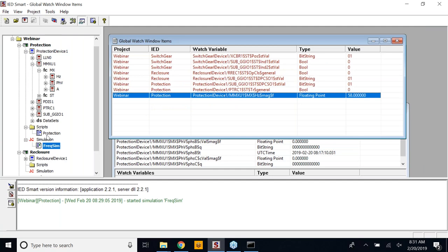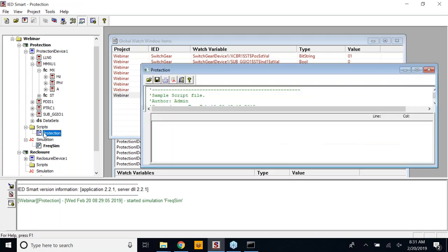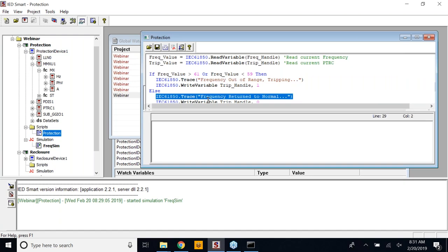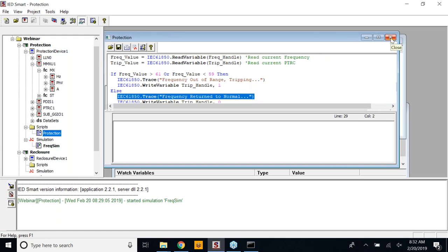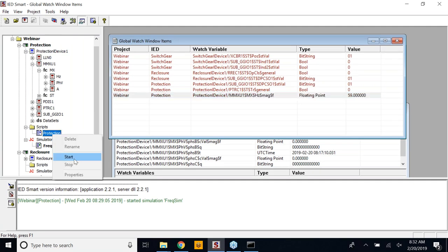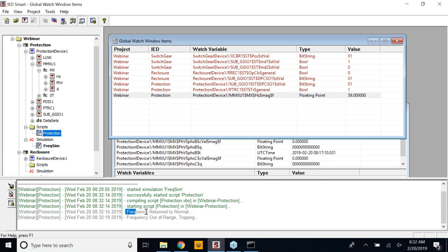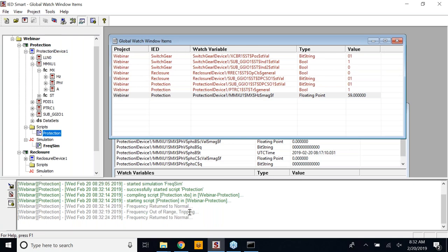I will run the script. There are certain print statements available and a trace — you will be able to see these two traces as the system detects these signal conditions. I will run this manually. Now you could see that the frequency has returned to normal — that's the first condition triggered — and now it is tripping. As the signal crosses 61 to 62, the trip signal will be invoked automatically, and this trip signal is sent out to the other device.